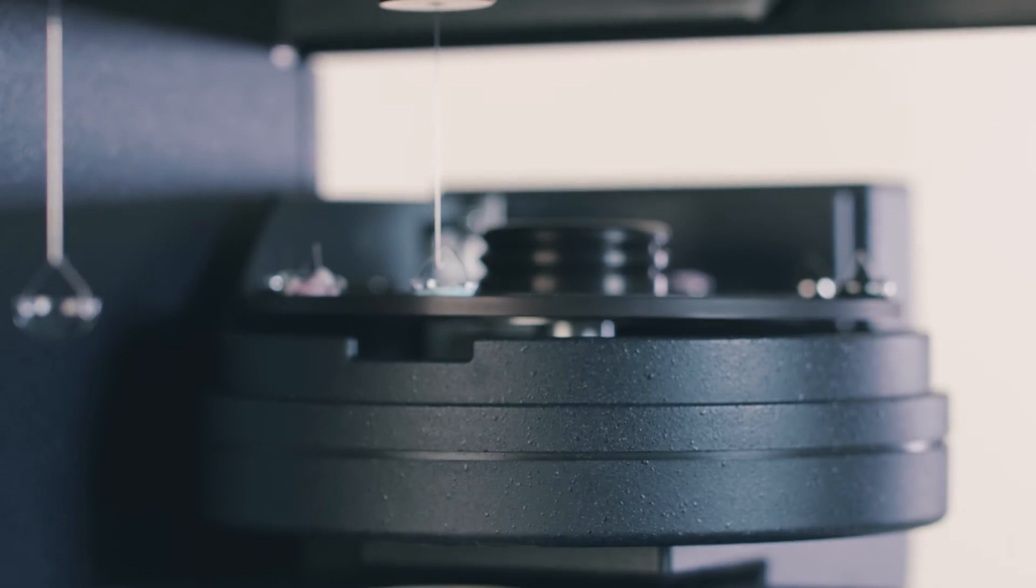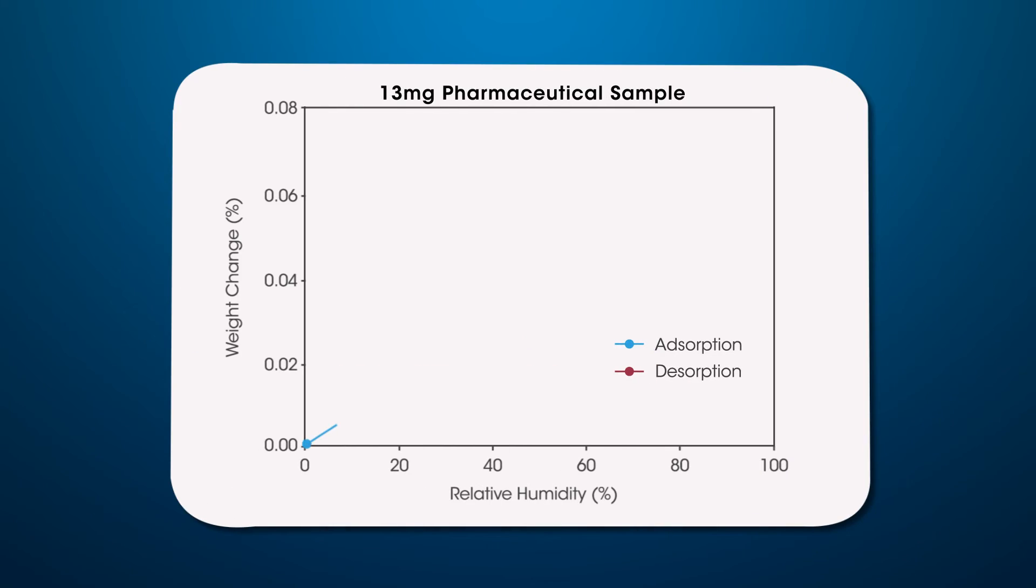The sensitivity of the Discovery SA is critical to address the most challenging sorption analysis applications. The data in this plot shows the sorption behavior of a 13 milligram sample of a crystalline pharmaceutical material which exhibits less than 0.1% weight change over a broad range of humidity. This corresponds to less than 13 micrograms of measured change.